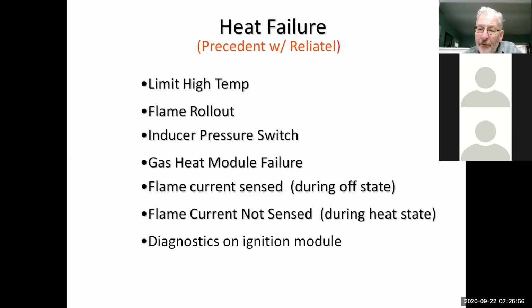Now, the funny thing with these units is if the limit switch fails, initially it'll give you a heat fail, but when you reset the power, if the limit switch doesn't reset itself, it's going to ignore the heating system completely, and it's not going to throw you any more codes. But when that happens in the test mode, it will just jump over the heating test. So if the high limit temp fails completely after you reset the power, you may not see that heating section. So it's got some quirks to it that you need to know about when you're working on them.